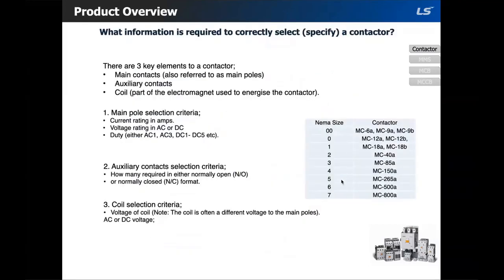The contactor is probably one of the most common components in an industrial motor control application. Selecting one correctly requires some detailed information to be provided. So what information is required to correctly select or specify a contactor? So there are 3 key elements to a contactor. So main contacts, also referred to as main poles, auxiliary contacts, and then coil, which would be a part of the electromagnet used to energize the contactor.